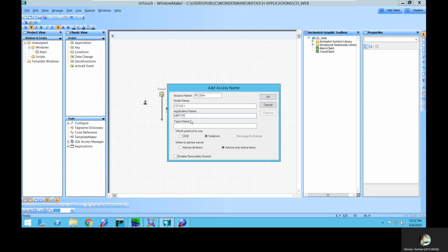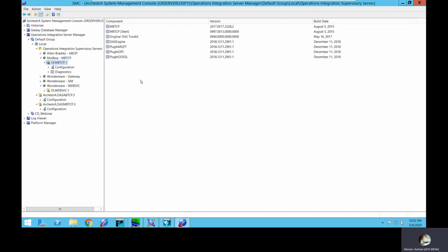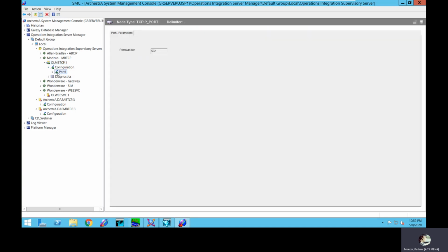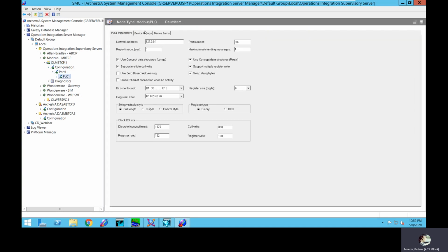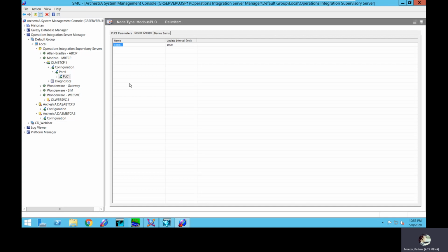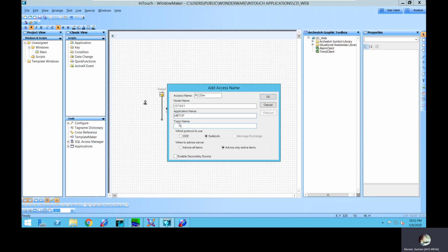mbtcp, and topic name. Topic name must be an existing topic, something that we already put. It's the device group, so it must be this one or another one. If you have topic 1, topic 2, topic 3, whatever you put here, it's up to you, but you have to use the same one there. Any misspelling will cause non-communication. It will not connect. So topic 1.